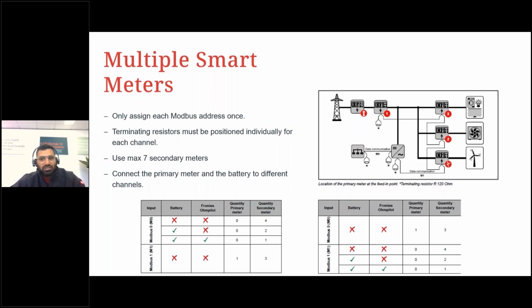And the Modbus connection between meters is just a series connection. So please make sure that the terminating resistor is installed only at the end of the line.